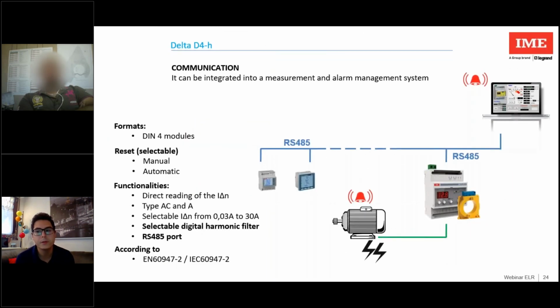So, special mention goes to one of the last born of the Delta family, the Delta D4H. In addition to the classic parameters already mentioned, it differs by the RS485 port, which allows you to remotely operate, reset, and control the differential current on an enhanced filter for digital harmonics. This is more or less the link between the type A or AC and the type B, which we will show you later. Well, but an ELR isn't only a relay.